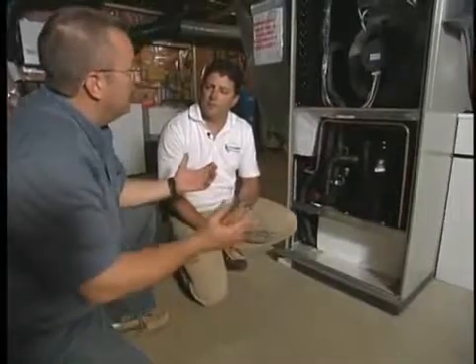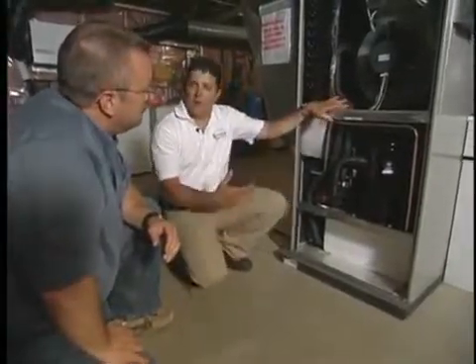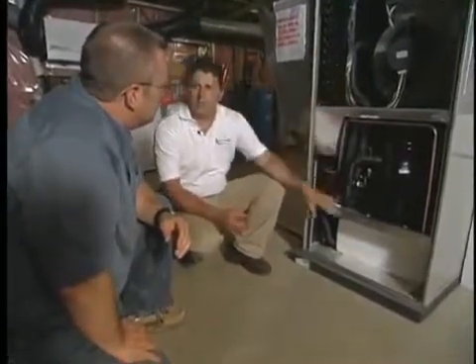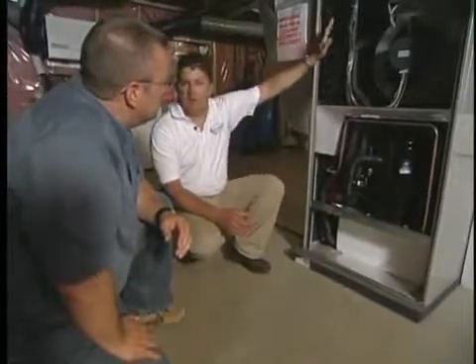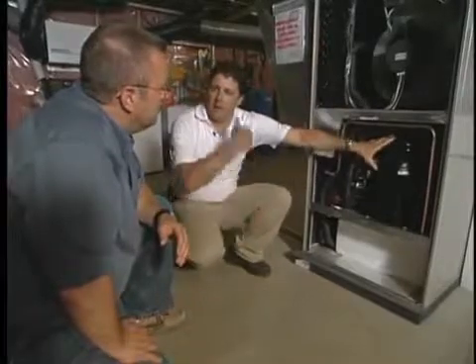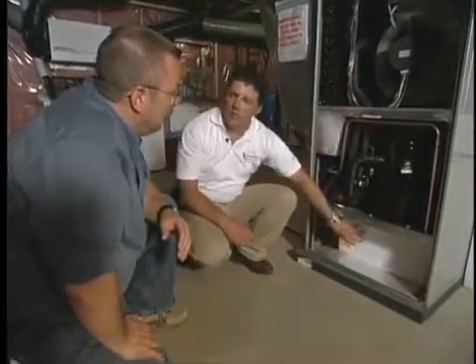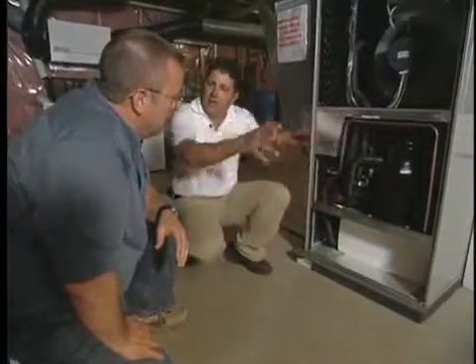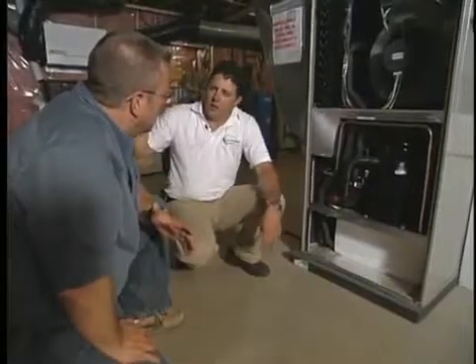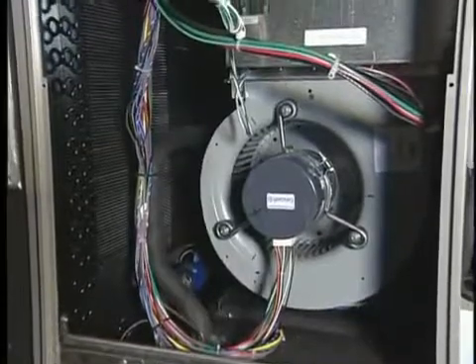Okay, what about in the summertime when we want to cool our homes? Well, that's a great question. In this machine here, there's a valve called a reversing valve, and what that simply does is reverse the flow of energy. We still have the two heat exchangers. Now we're blowing warm air across this heat exchanger, absorbing the heat energy again. We're still intensifying because we've got to remove the energy with the compressor, and we're taking all that heat energy and putting it into this heat exchanger, which is dumping out into the nice cool ground. So instead of having an air conditioner sitting outside your home working hard when it's 95, our air conditioner is working at 50-degree ground temperature, so it makes it more efficient.